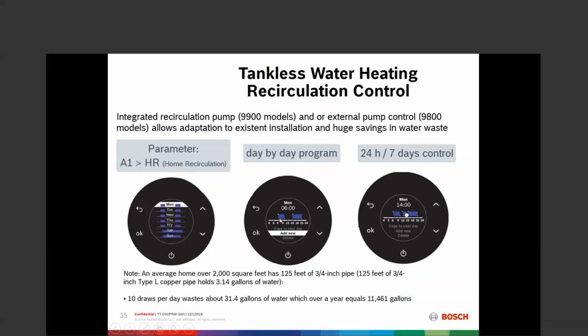At 6 o'clock in the morning, whether it's an onboard pump or an external pump, either way, it doesn't matter. The unit powers the pump. It's going to energize the pump, act as a switch for the external pump, and actually power the internal pump. The circulator comes on, pushing water around the loop, and the water's coming back to the unit. When that water comes back to the unit within 10 degrees of set point, the logic on the board is then to power down that circulator, shut that circulator off.